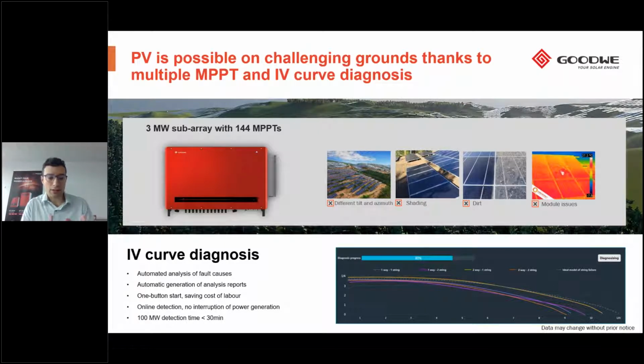The IV curve diagnosis is a feature that also helps for remote operation and maintenance. With one push of a button remotely, the system will make an intelligent analysis of the fault causes. It will report any faulty strings, and it will be self-learning over time based on irradiation and other external factors, taking all of that into consideration and providing the right advice to the operator of the power plant. This online detection happens without even interrupting the power generation of the power plant.